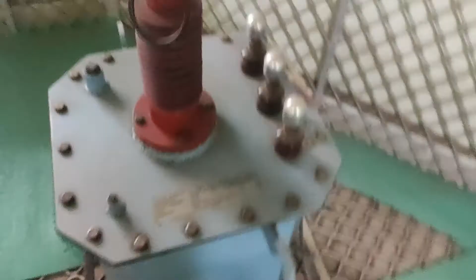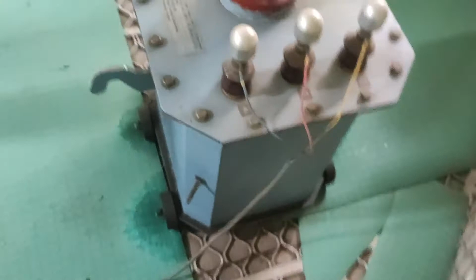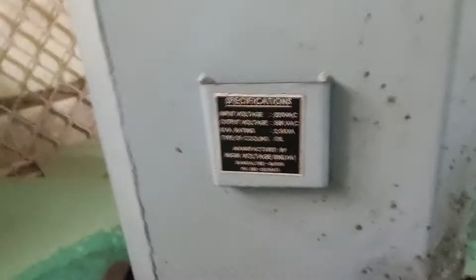We will observe the internal structure of the transformers inside the Faraday cage. Here you can observe the output of this control panel is given inside the Faraday cage, and you can observe the wire moving towards the transformer setup. So this is one transformer in which you can observe the different connections, electrodes. This is the HT side of the first transformer, and you can observe its nameplate. Here you can clearly observe its rating also: input voltage is 200 volt, output 100 kV AC, 2.5 kVA rating, and oil is used as the cooling medium.